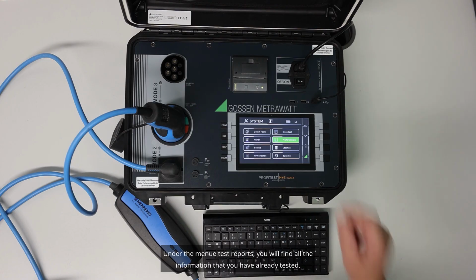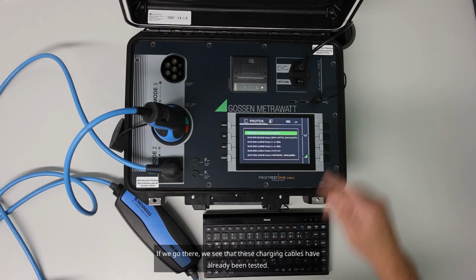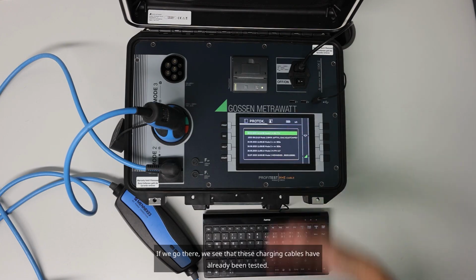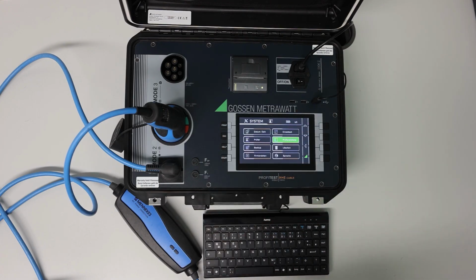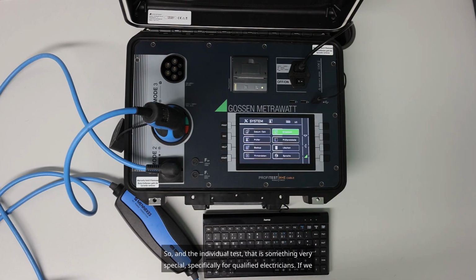Under the menu Test Reports, you will find all the information that you have already tested. If we go there, we see that these charging cables have already been tested. So, and the individual test, that is something very special, specifically for qualified electricians. If we get an error message or locate an error ourselves, you have the option to carry out the tests here in the individual test.